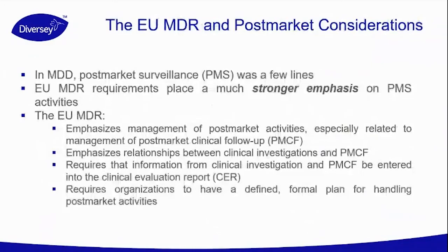In the MDD, post-market was only a few lines, but the MDR places much stronger emphasis on post-market surveillance activities. The EU MDR really emphasizes management of these post-market activities, the relationship with the clinical evaluation and investigation, and really requires the manufacturer to have a defined formal plan for handling the post-market surveillance activities.